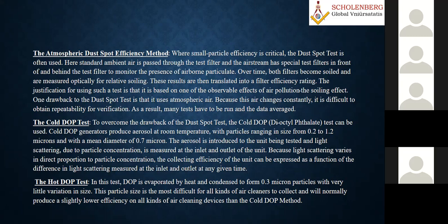So what is the drawback of this one? It uses atmospheric air, and the air changes constantly. It is difficult to obtain repeatability for verification. As a result, many tests have to be run and the data have to be averaged. It is not one day or two days. All these data are averaged, and then you have to go for the mean, the regression, or the regression analysis and all of that.